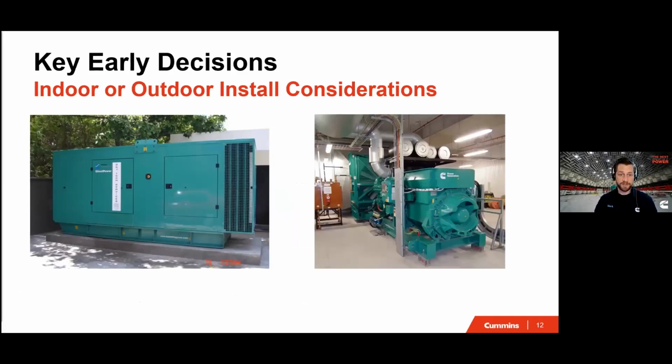The next key decision point that comes to my mind is the physical location. And I know a number of you cited this in the chat, the physical location and surroundings of the generator set. There is so much potential variety at play here, and I can't enumerate all the differences to the finest detail. But one of the biggest drivers of key specifiable differences is whether the generator set will be installed outdoors in an enclosure or indoors in its own dedicated facility. One is not inherently better than the other, but each method has its own set of positives and key watchouts to work with.